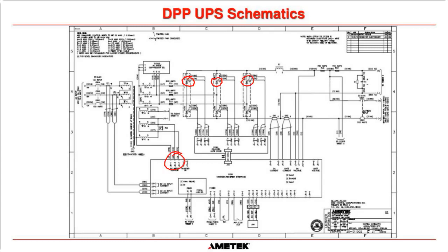This is where the board gets its 3-phase input to know when to turn on the SCRs, well, the reference signal. We have this TH1, a thermocouple attached to the heatsink that these SCRs are connected to, looking to see if there's something wrong and the SCRs are getting too hot. If that closes, and that closes at 90 degrees C, not F, 90 degrees C, which is bloody hot, then it will shut down the rectifier to protect itself.